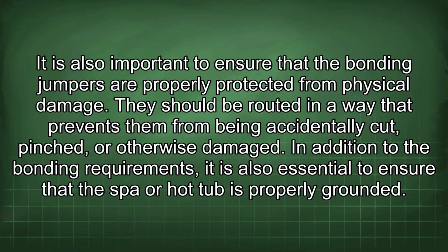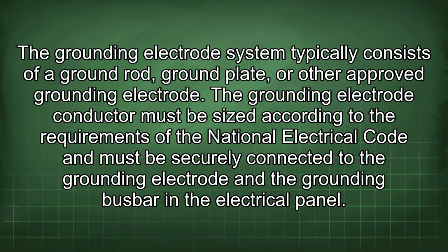They should be routed in a way that prevents them from being accidentally cut, pinched, or otherwise damaged. In addition to the bonding requirements, it is also essential to ensure that the spa or hot tub is properly grounded. The grounding electrode system typically consists of a ground rod, ground plate, or other approved grounding electrode. The grounding electrode conductor must be sized according to the requirements of the National Electrical Code and must be securely connected to the grounding electrode and the grounding busbar in the electrical panel.